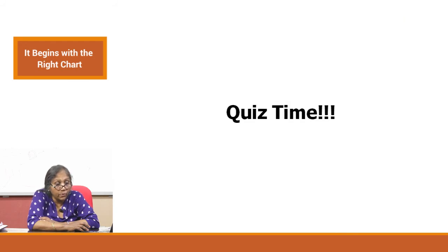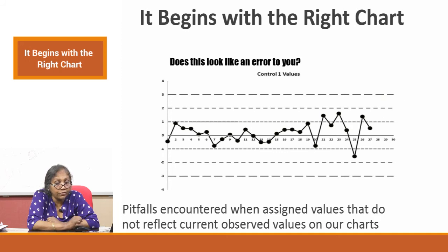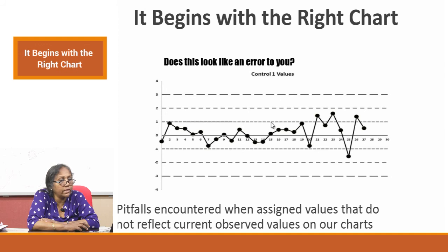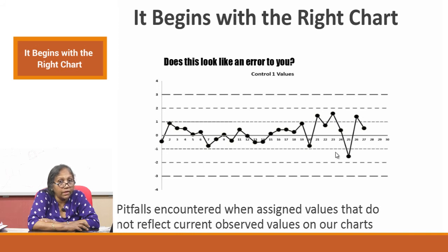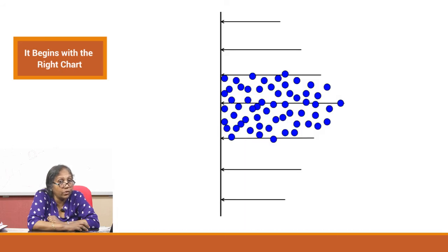Let us look at a quiz using a graph from a published paper. This is level 1 control values, and from around the 18th run onwards, you see some fluctuation. You might say it is okay because it is within the 2 SD limit. But was this correct to start with? No — you cannot have all your runs sitting in the 1 SD region. Looking at it on a Gaussian, all points are coming in the 1 SD region, which is not how a Gaussian works.